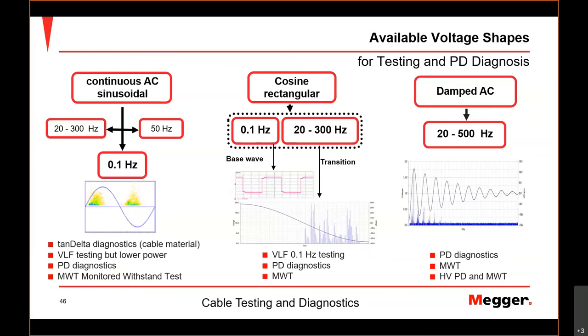So it's a relatively long time where people do say, well, we don't want to wait that long. If you monitor your test with partial discharge, for example, and you do not see any partial discharge from the beginning of your test, well, then you can be pretty sure there are no electrical trees growing. So I do not have a bad effect started that I would need to finish. They haven't even started, because these electrical trees are practically partial discharges. That way you can say, okay, I can stop my test earlier.